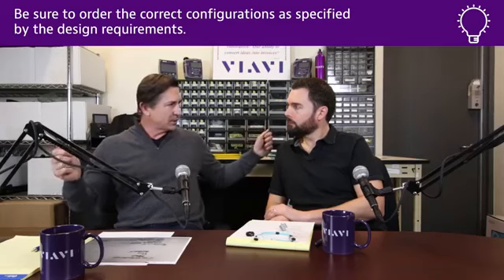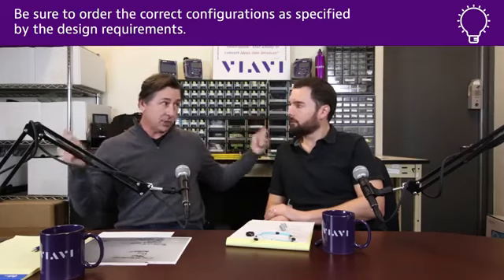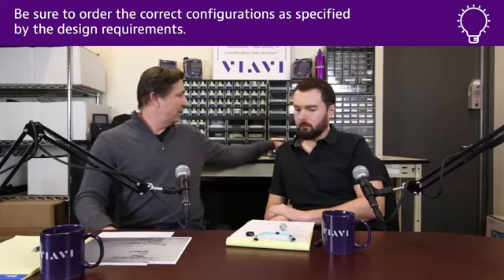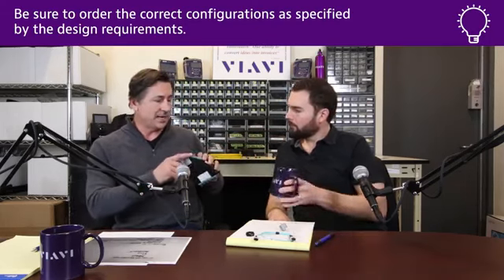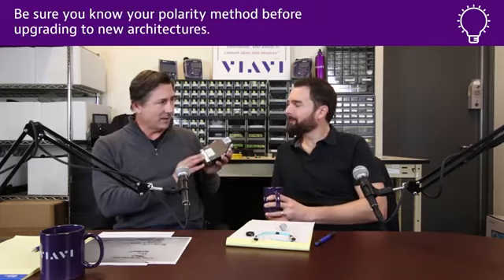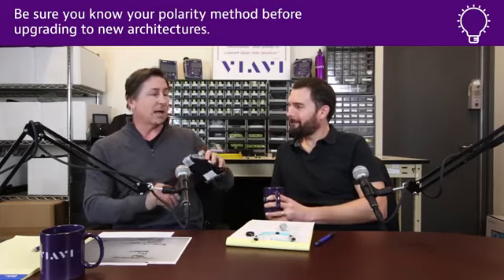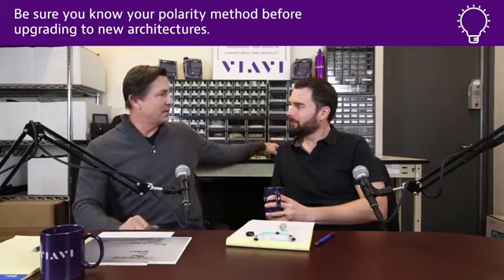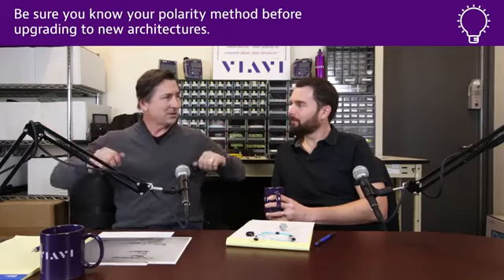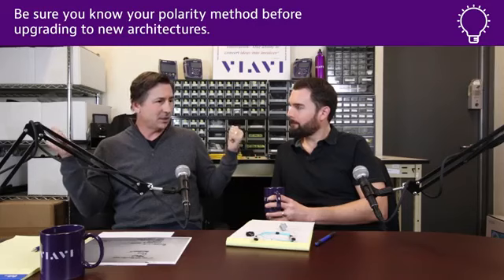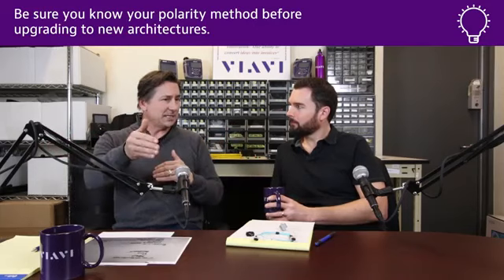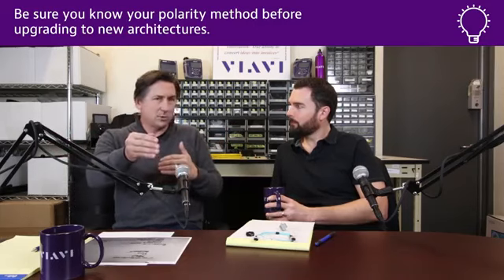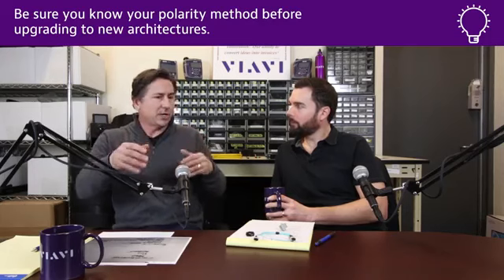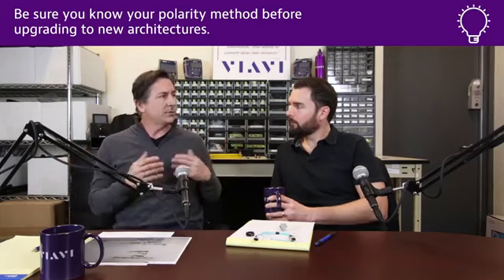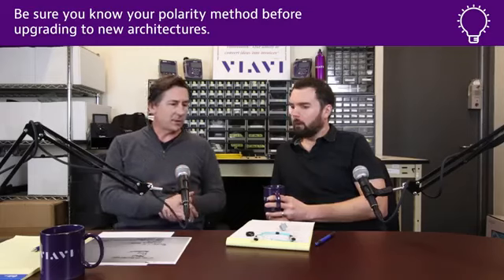Now somebody comes to turn up services and add patch cords. Are they using the right patch cord for the system? Or you had a legacy system that was MPO, that had MPO trunks, an upgrade scenario, and went to LCs, and now you're saying, I'm going to go parallel optics. I'm going to rip out the module, put in a panel, I've got my MPOs, and I'm going to connect through to the QSFP. That's a legacy built system. I don't know when those trunks were put in, years ago. Now, are you getting the right patch cords? So there's a lot of ways for it to go wrong.